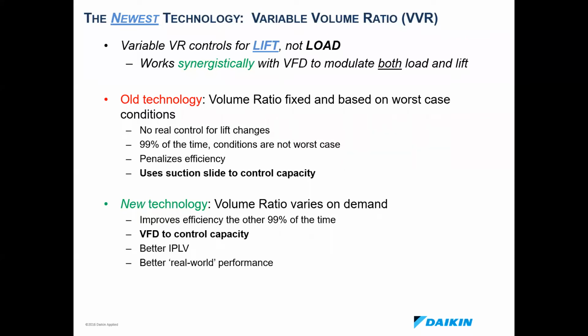So our compressor today is able to modulate for both lift and capacity simultaneously to optimize for part load conditions, whereas before you could only really modulate for your capacity, which doesn't give you nearly as much control, and it doesn't really handle the part load scenarios as well as the new technology.